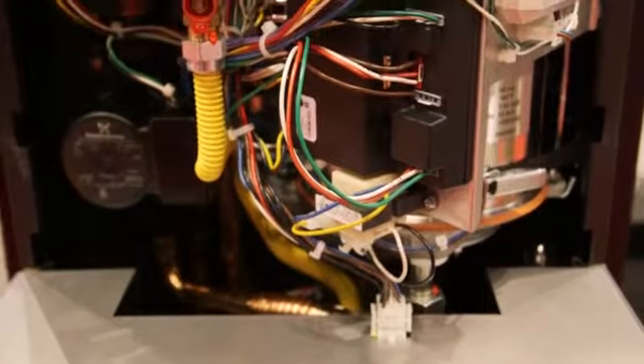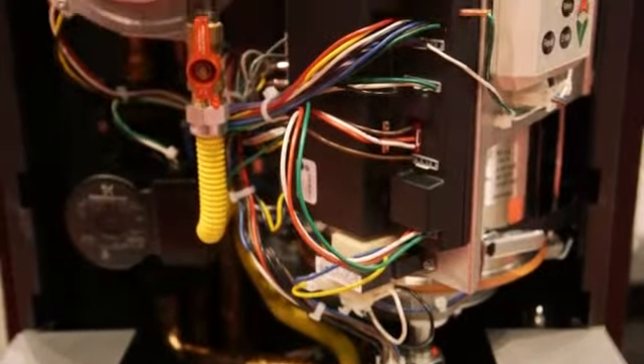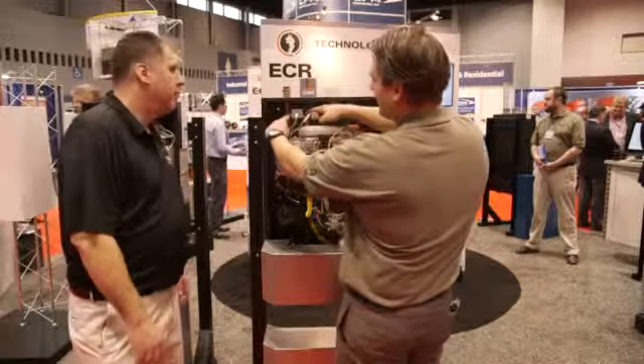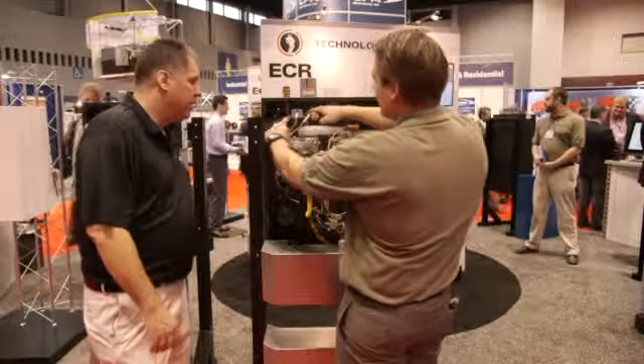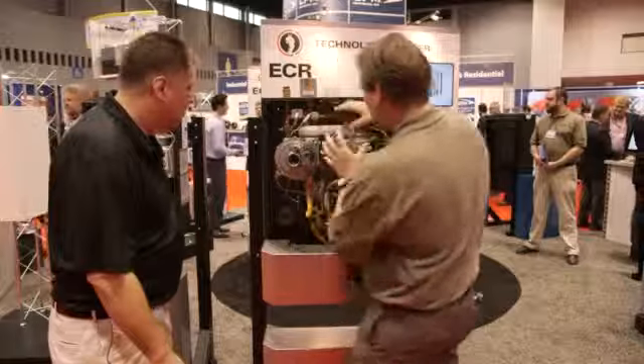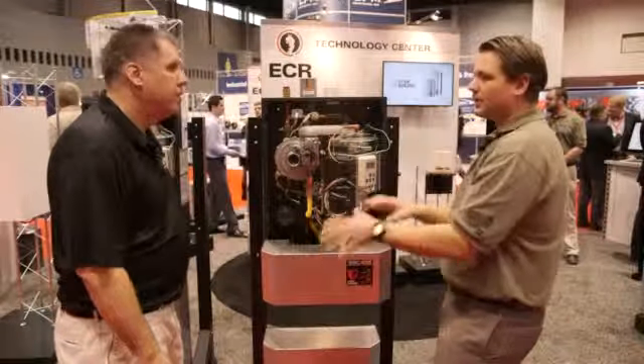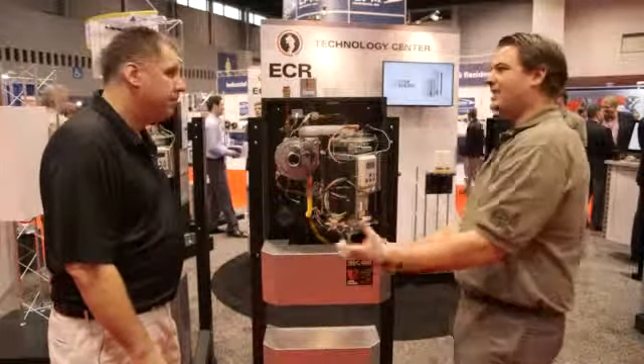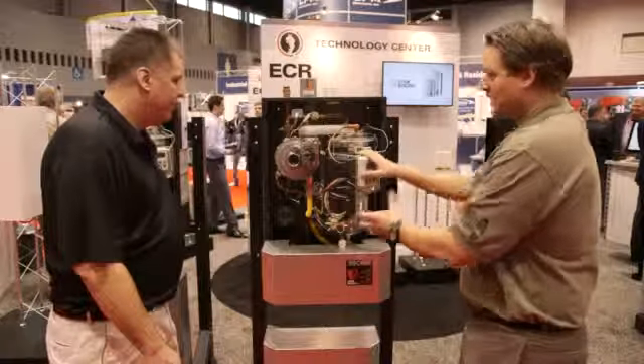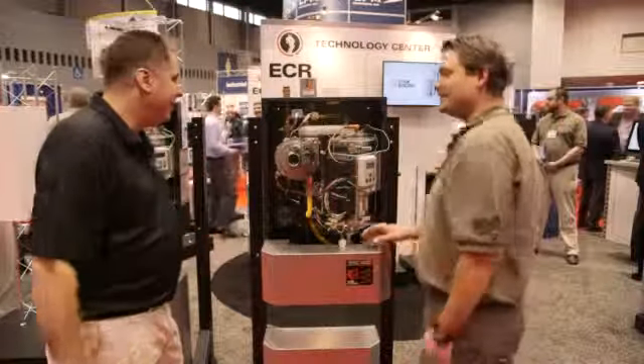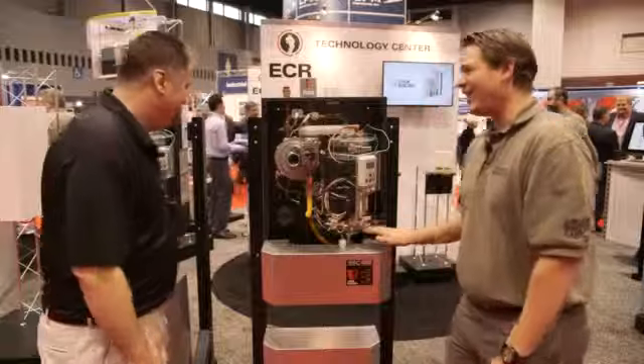Well, show me where the primary, secondary is and how it's piped in. Well, you've got the primary, secondary up here. These are really your closely spaced tees. All right, you've got the internal pump running the boiler only. So you still have to add one external pump. Sure. But if you can do a cast iron boiler, you can do one of these. Pipe it in, pipe it out. That's it. Even I can figure that one out, Simon. We all can, right?